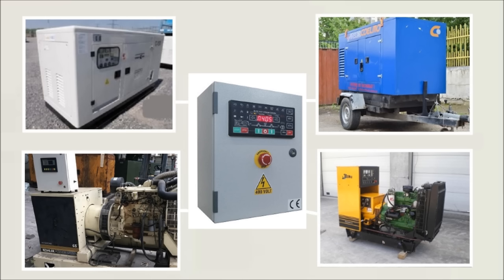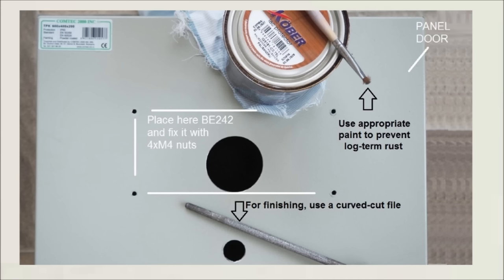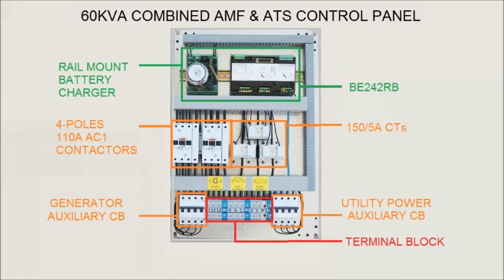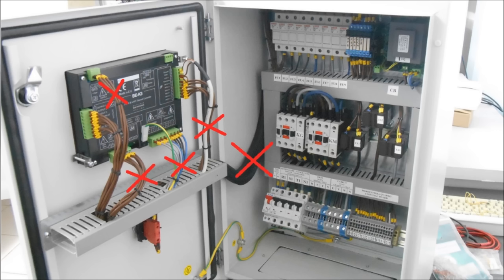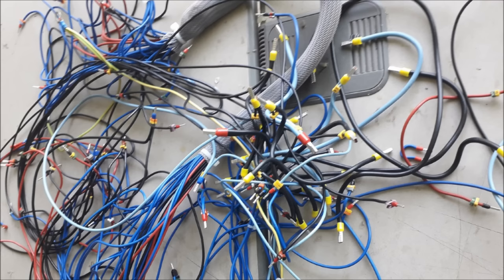Benefit number one: you save 50% time in making a panel. You make a round hole on the door; all 400 volt connections are made in the backplane panel, so there are no AC cables connecting to the front door. You save 20 meters of cables, and there's no interference with low voltage circuits in case of lightning. This means really long-term reliability.